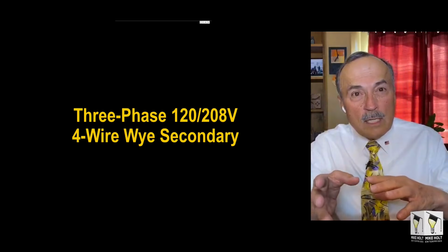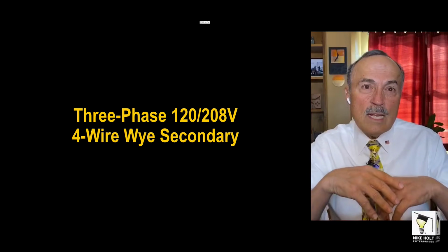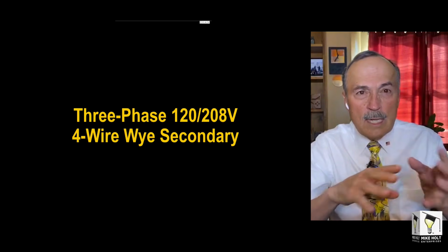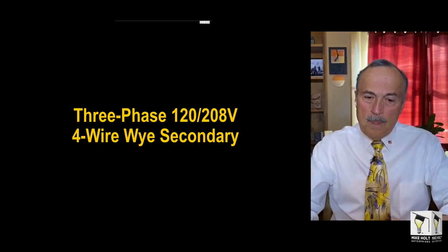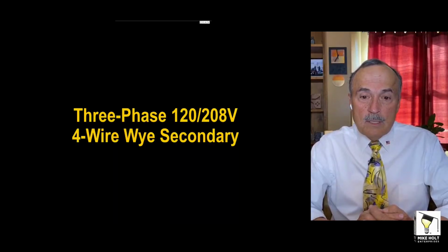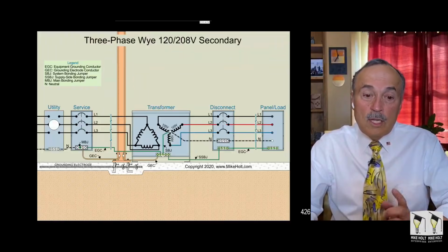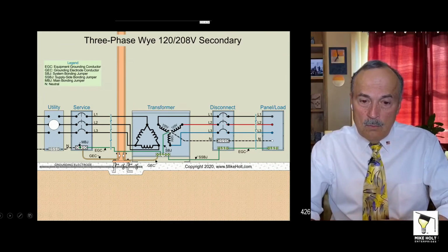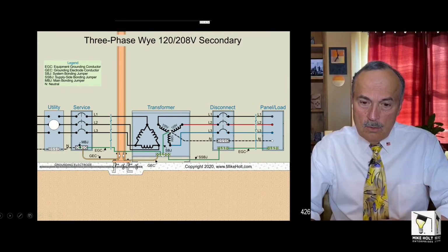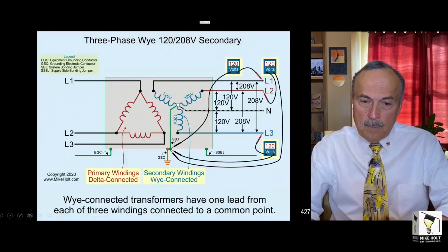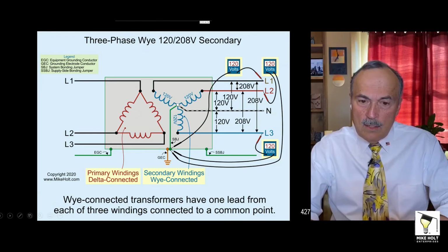You're going to have your criteria. When do you go to 277/480? When do you go to 120/208? And that's not the scope of this program. All right, I'm sorry, this is going to be 120/208, 4-wire. We have 3 phases and a neutral. There's 4-wire, no problem. 120, 120, 120 is going to be the phase voltage.